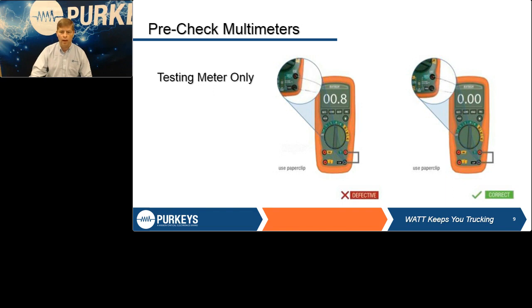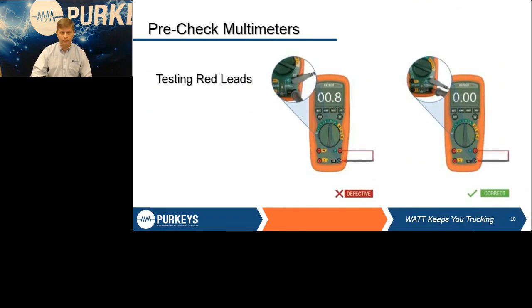If it doesn't zero out doing this, it tells you, hey, it's not a lead problem, it's a meter problem. That's one of those things, again, you get what you pay for. Buy a good meter, something that has a calibration program, so that if it does get out of calibration, you can send it in and get it calibrated to make sure it's in good working order. If it did zero out, we're going to check our leads. Doesn't matter which one you do first, but first we're going to do the red one.